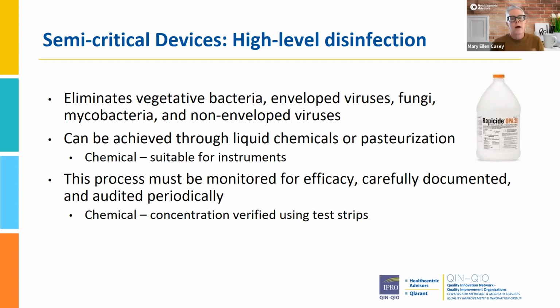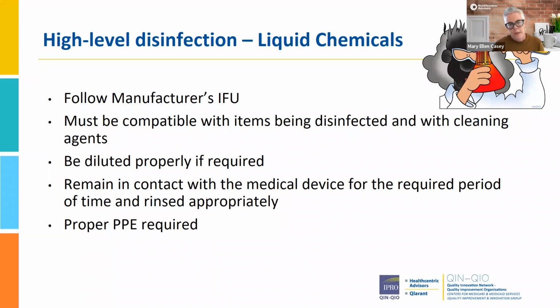It's not only the process of doing the high-level disinfection, you also have to monitor it for safety. It has to be documented, it has to be audited. The chemical concentration itself has to be checked and verified using test strips. This is another example of following manufacturers' IFUs, because you want to make sure that the equipment being dunked into this chemical solution is actually working. It must be compatible with the items that you're disinfecting and cleaning. It has to be diluted properly in some cases. It has to remain in contact with the medical device for the required period of time and rinsed appropriately.